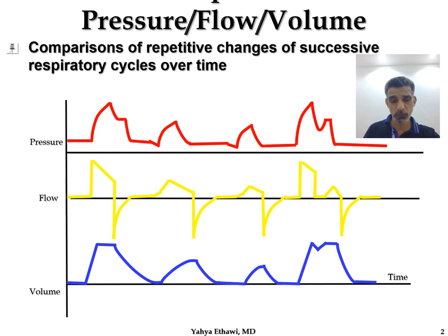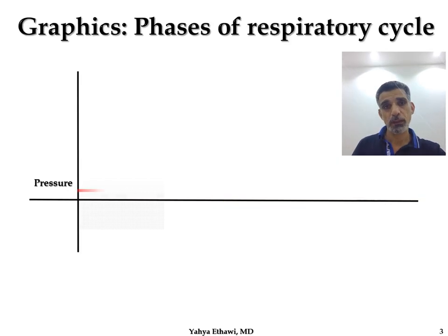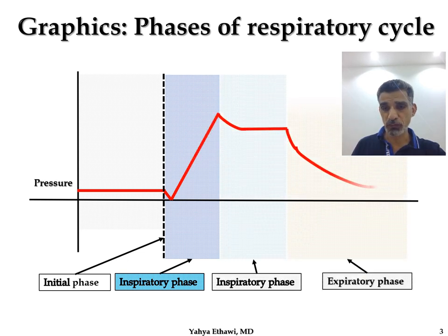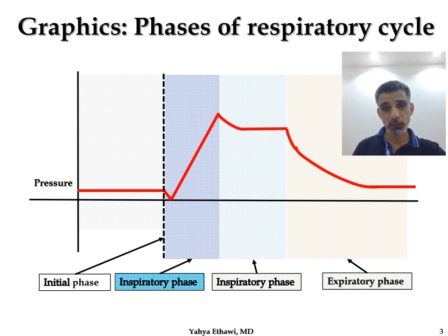You can see we are achieving the tidal volume in the third line — in blue color — in the first breath and also in the last one, although it's not synchronized. In the second and third breaths, we are not achieving the tidal volume. The machine knows the phases of ventilation depending on time, pressure, or flow — it delivers in from one time to another, and out from one time to another, or changes phase when the flow changes.